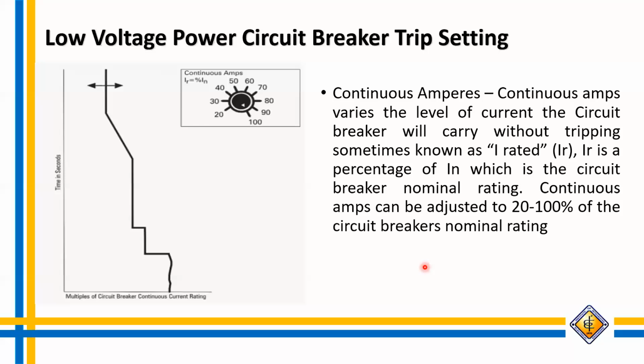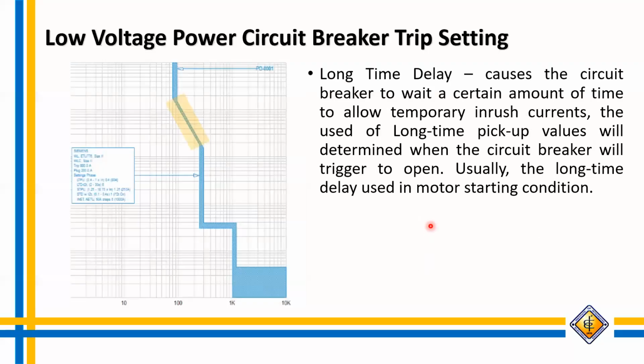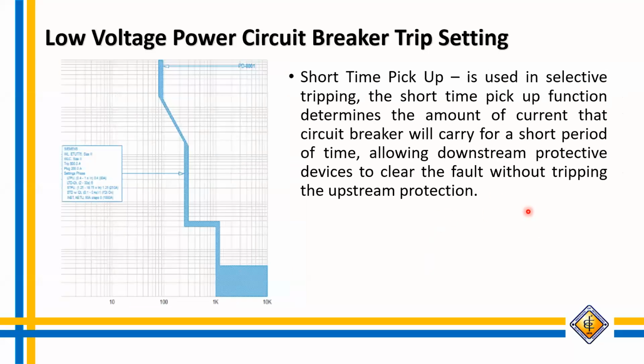So it is adjustable. The long time delay, if you don't have any motor control protector, can be used. This tripping capability can be used in long time pickup values that will determine when the circuit breaker will trip or open. Usually, the long time delay is used in motor starting condition. The short time pickup is used in selective tripping. The short time pickup function determines the amount of current that the circuit breaker will carry for a short period of time, allowing downstream protective devices to clear the fault without tripping the upstream protection.